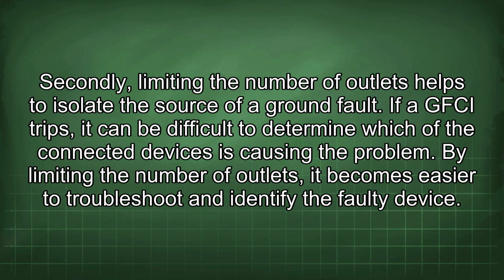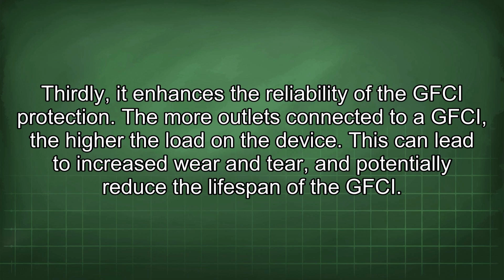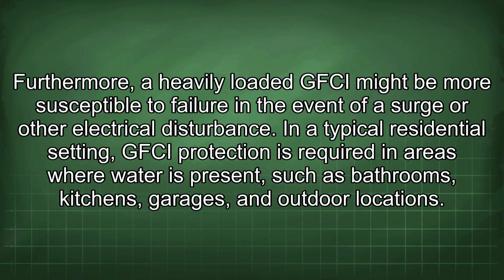Secondly, limiting the number of outlets helps to isolate the source of a ground fault. If a GFCI trips, it can be difficult to determine which of the connected devices is causing the problem. By limiting the number of outlets, it becomes easier to troubleshoot and identify the faulty device. Thirdly, it enhances the reliability of the GFCI protection. The more outlets connected to a GFCI, the higher the load on the device. This can lead to increased wear and tear, and potentially reduce the lifespan of the GFCI.